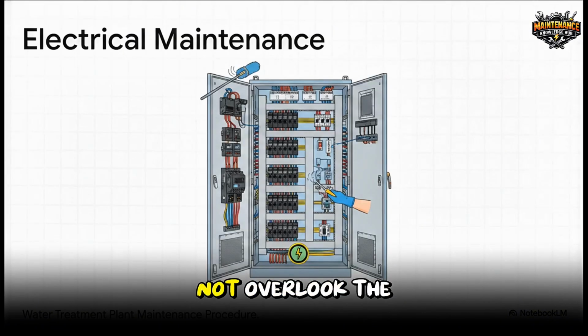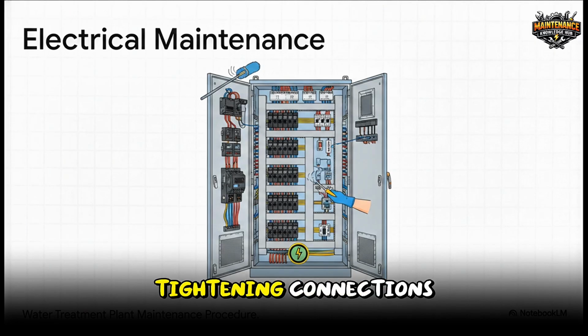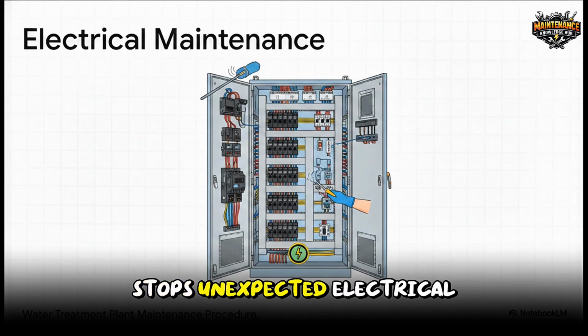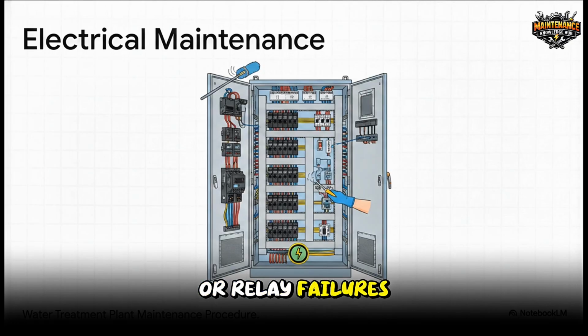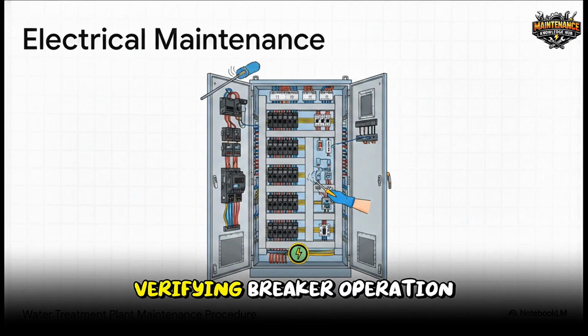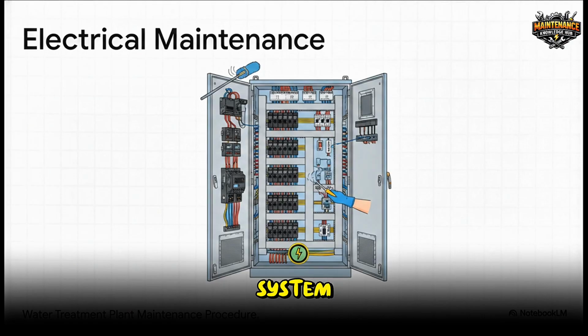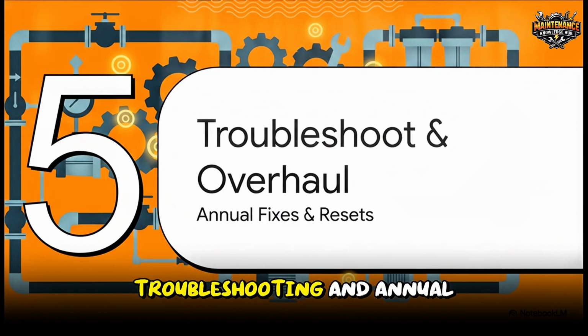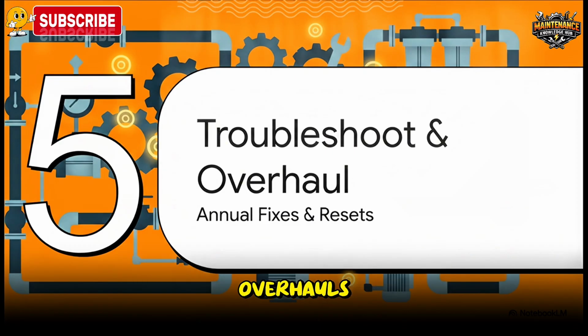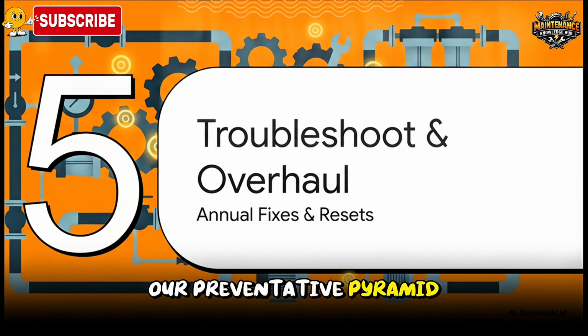And please, do not overlook the electrical side. Your motor control center, your MCC panels, they are the actual brains of the operation. Doing something as simple as cleaning dust out of these panels and tightening connections stops unexpected electrical fires or relay failures dead in their tracks. Verifying breaker operation and your earthing system guarantees that if a fault does happen, your people and your equipment are protected. Finally, Section 5, Troubleshooting and Annual Overhauls, the top of our preventative pyramid.